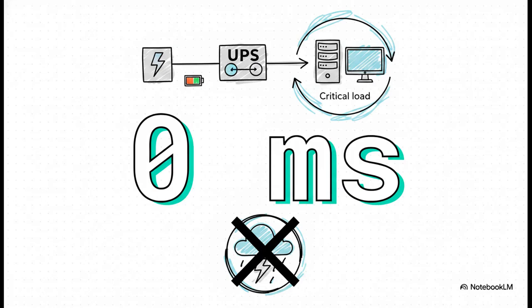And because of that brilliant double conversion process I just described, the transfer time for an online double conversion UPS is exactly 0 milliseconds. Zero. No way, right? But it's true. This is incredibly exciting from an engineering standpoint. Because your equipment is always being fed by the inverter, rather than directly from the wall, there's absolutely no switchover time when the power goes out. The grid fails, the battery just seamlessly keeps feeding the inverter, and your critical load experiences true power isolation. It never even knows a storm is happening outside.